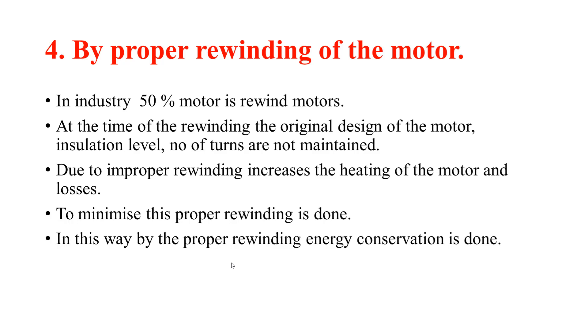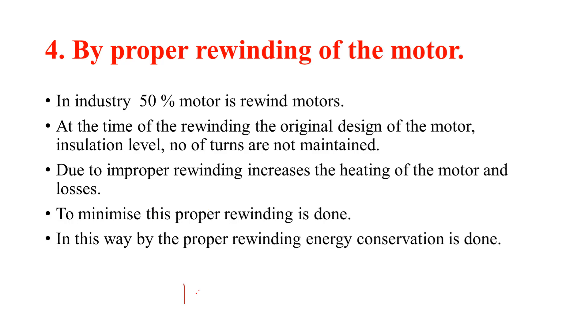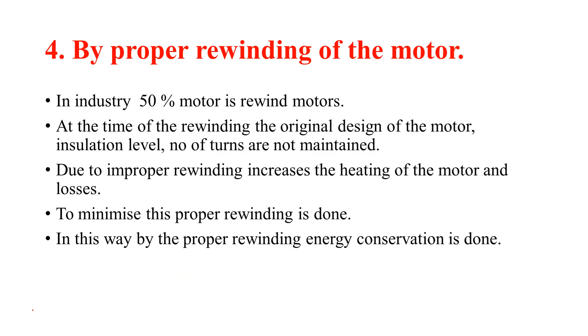If you have poor winding where the insulation level is poor, losses increase and energy is wasted. To reduce losses, you must maintain proper insulation level, wire size, and number of turns according to the original design. By using the correct new design and implementing proper rewinding, losses are reduced and energy conservation is achieved.